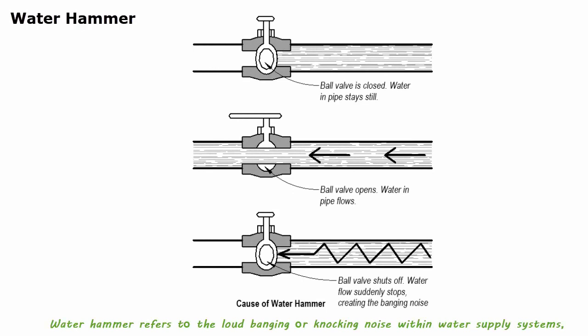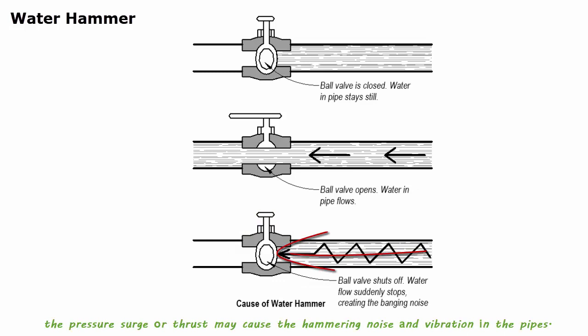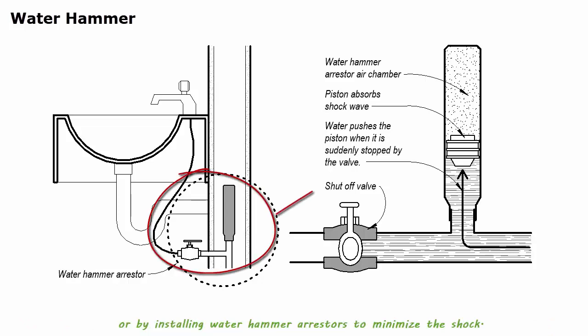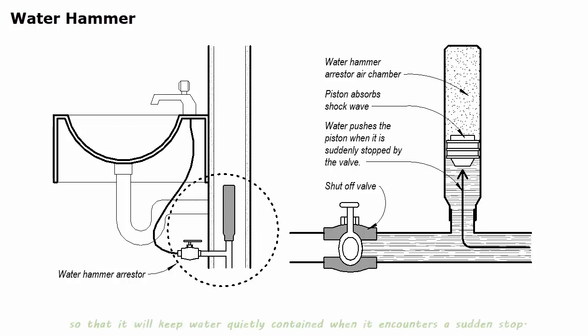Water hammer refers to the loud banging or knocking noise within water supply systems, as if the pipes are being hit by a hammer. It is a result of sudden changes of water flow through pipes. When water movement is stopped with a sudden force or direction change, the pressure surge or thrust may cause a hammering noise and vibration. Water hammer can be reduced by decreasing water supply pressure with a pressure regulator, or by installing water hammer arrestors. An arrestor has a chamber full of air that compresses when water enters it, cushioning the water so it stays quietly contained when it encounters a sudden stop.